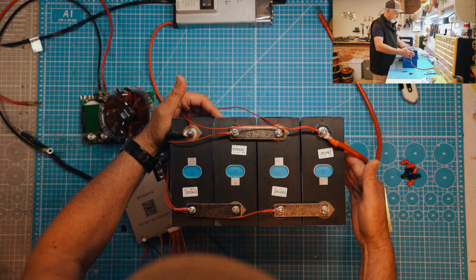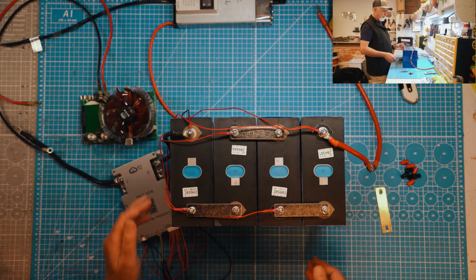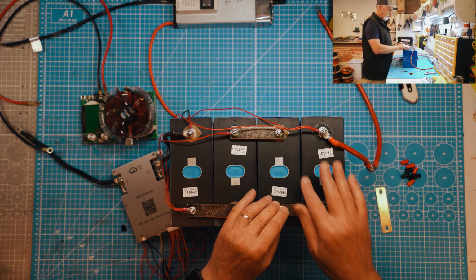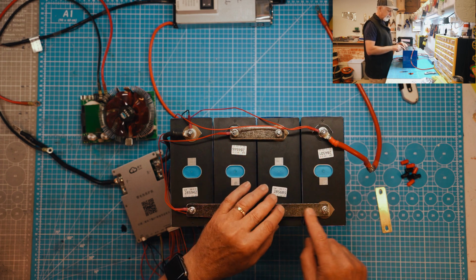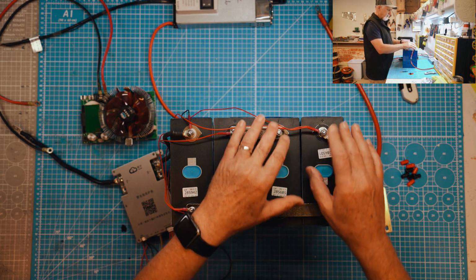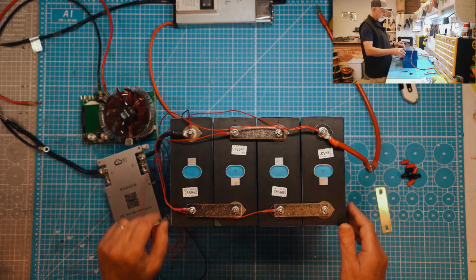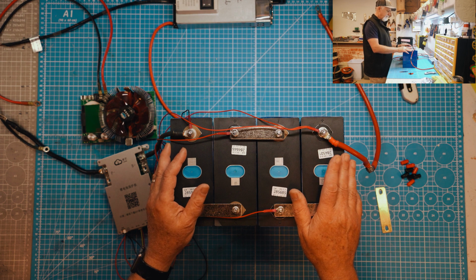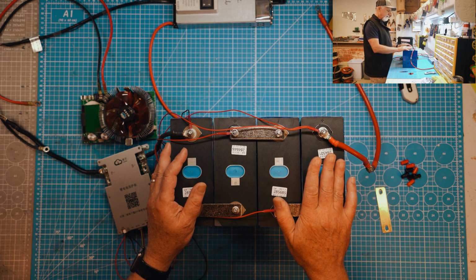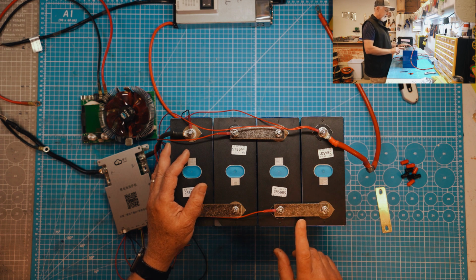Now that they are charged, I'm looking a little bit at how much they have swollen. Because when this was put together, these were all in parallel. As you can see, the bus bar is holding these two together, but they've swollen, so this is forced out here, and although you can't see it very clearly in the camera at the bottom, they're forced quite far apart, so they've splayed out as a result of the swelling. Now, all cells do swell, but not as much as these, so I have to say I am concerned with the degree to which these have swollen. We've known cells to swell much more than these, but the ones we put into our batteries will only swell by about 1 mil, and this has swollen quite a lot more. So a little bit concerned about that.